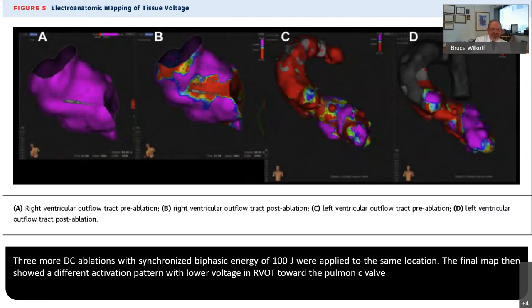And they were unipolar, so monophasic and unipolar, going to a grounding pad, and it would melt the platinum that was in the electrodes. So you got one shot with every catheter. With this being between 70 and 100, this is a much lower energy, much lower current, with no evidence of causing the kind of destruction that was caused to the catheter before.